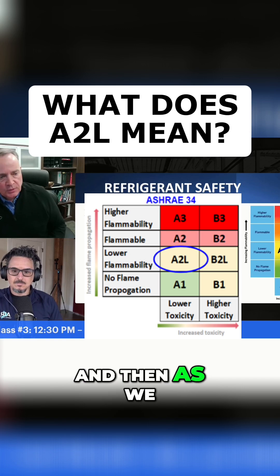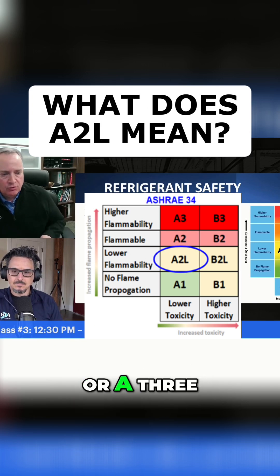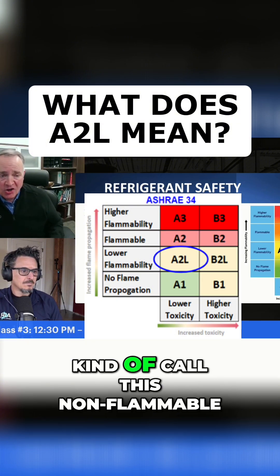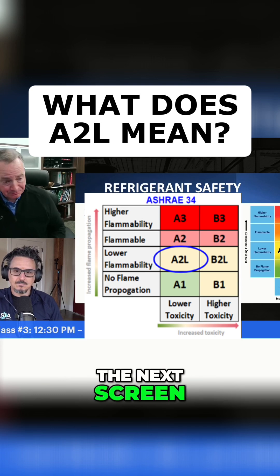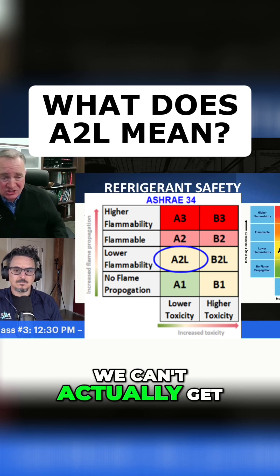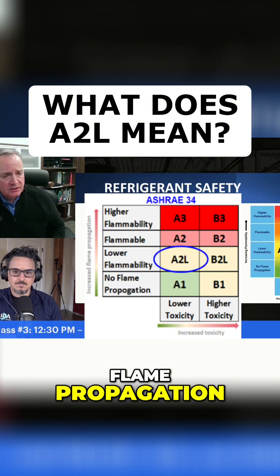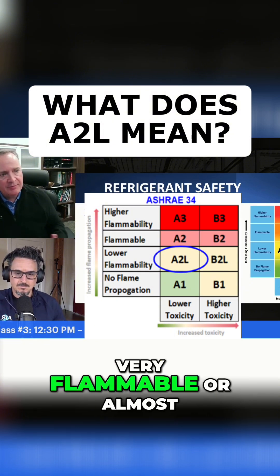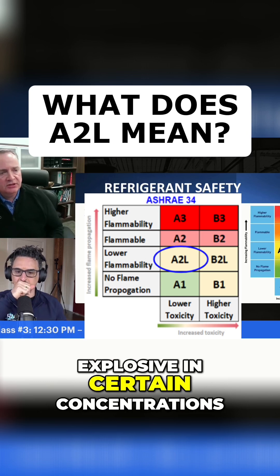The second digit is a 1, 2, or 3. A 1 is technically no flame propagation — a lot of people call this non-flammable, but as you'll see on the next screen, we can't actually get these to light. Then we have 2 for flammable, and 3 for higher flammability — very flammable, or in some cases even explosive in certain concentrations.